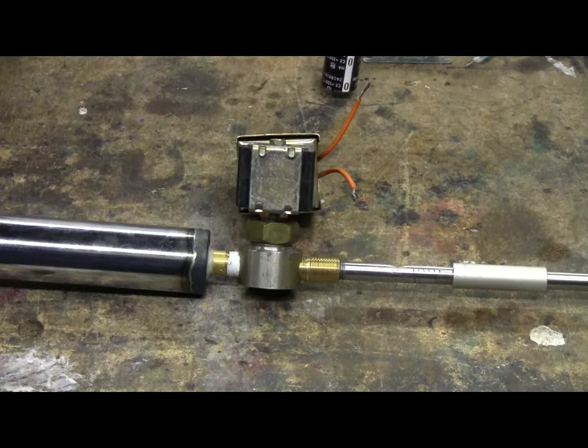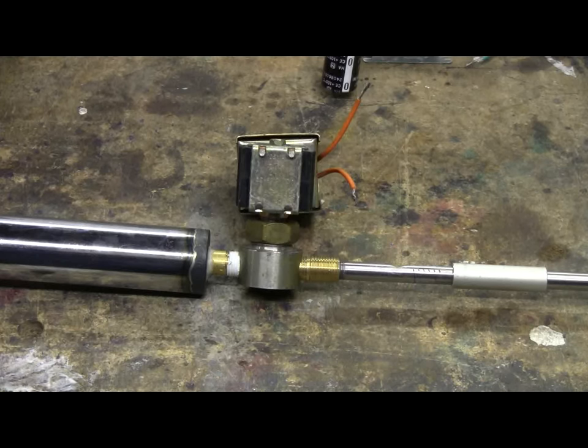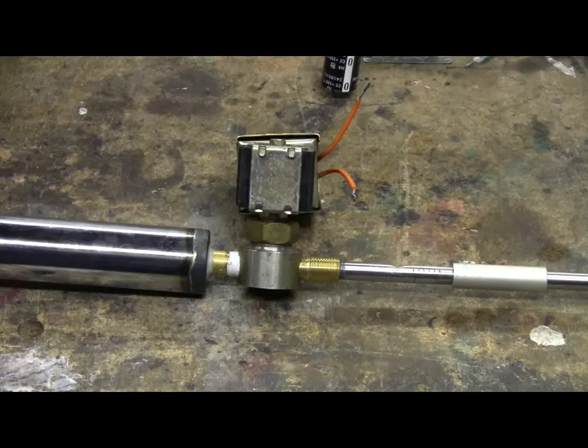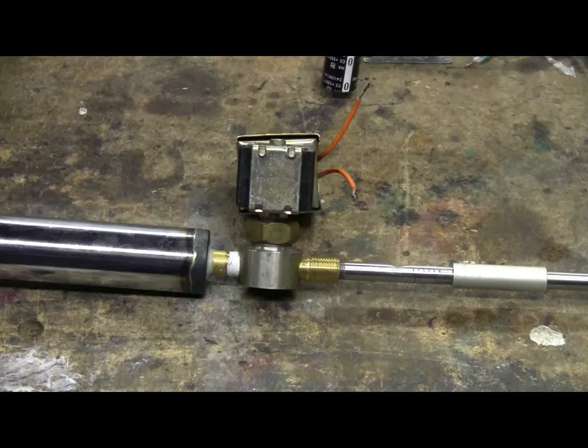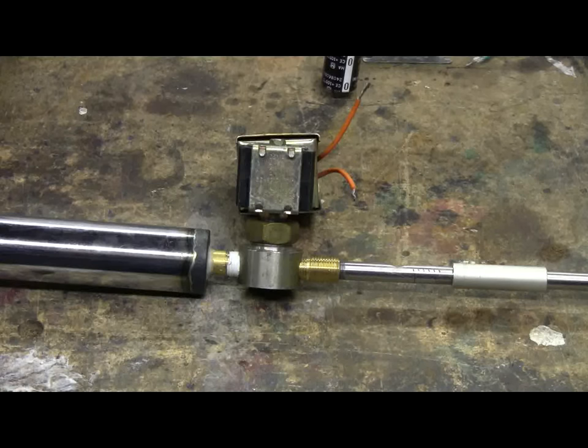One problem I've run into with these little 24 volt solenoid valves is that at higher pressures they will not open on AC. So I'm going to demonstrate this problem and then show a quick fix workaround for it.